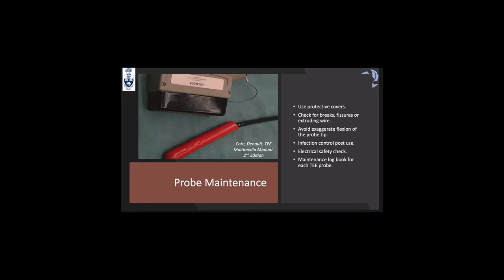Probe maintenance: it is recommended to use protective covers for the electrical connector and the tip of the probe. Before inserting the probe, check for breaks, fissures, or extruding wires due to electrical safety risk. Avoid exaggerated flexion of the probe tip as this can damage the esophagus or stomach. Infection control is required after use, and an electrical safety check is needed if you see any fissures, breaks, or extruding wires. It is also recommended to keep a maintenance logbook for each TEE probe.